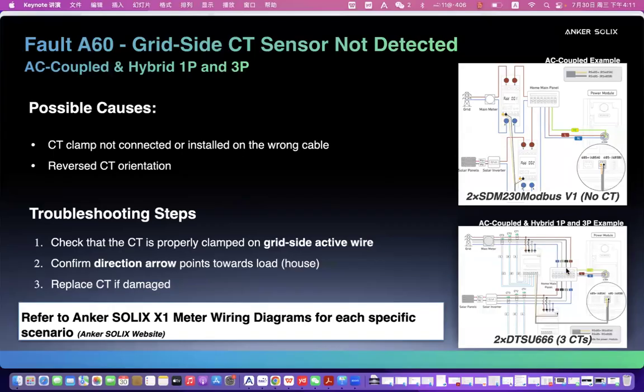But for the second part, this is a picture very frequently used. It's about our hybrid three-phase machine used as AC couple. What does this mean? It means in this home you have existing solar, so you need 2 meters. This is for grid side, and this is for PV side. If A60 happens, it must be this meter's fault, especially the CT is in the wrong phase or the CT is not pointing to the loads, it's pointing to the grid. So it will show this error. You just check with this diagram and change the CT direction or the CT's phase, and it will be all good and will pass the self-test.